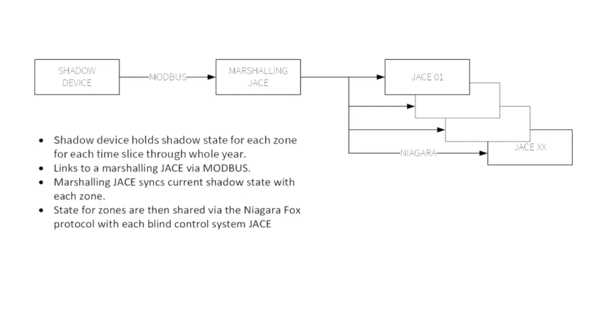We use them, as it says here, for marshalling. We bring signals from our shadow device and take those out to other devices that control the blinds themselves. The great thing about using the Niagara platform is that it's completely customizable, and it also talks to a lot of other systems - BACnet, MQTT, Modbus, MBus - all the protocols used inside BMSs, building management, and other intelligent systems.